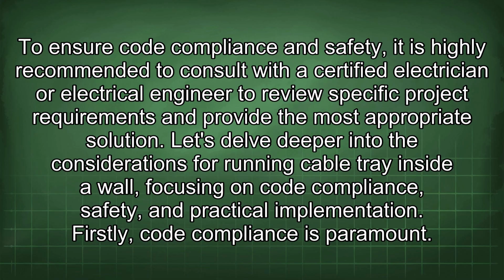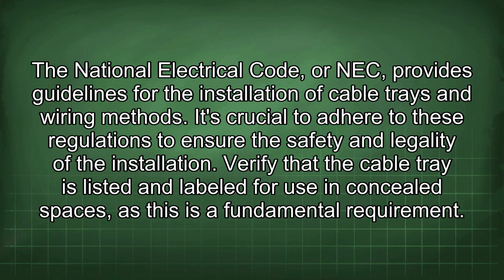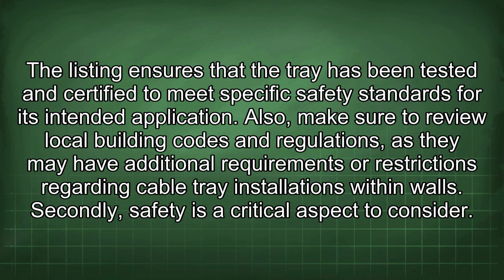Let's delve deeper into the considerations for running cable tray inside a wall, focusing on code compliance, safety, and practical implementation. Firstly, code compliance is paramount. The National Electrical Code, or NEC, provides guidelines for the installation of cable trays and wiring methods. It's crucial to adhere to these regulations to ensure the safety and legality of the installation. Verify that the cable tray is listed and labeled for use in concealed spaces, as this is a fundamental requirement. The listing ensures that the tray has been tested and certified to meet specific safety standards for its intended application.